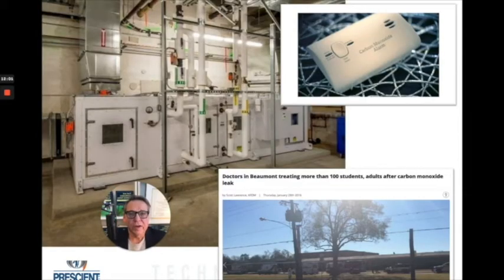Just how bad could it get? I was deposed a couple of months ago on a horrible incident that occurred in Beaumont, Texas at an elementary school. Close to 200 people were impacted when carbon monoxide in a mechanical equipment room got distributed through an air handler in the building and made lots of people sick. If you're in responsible charge of a mechanical equipment room that has naturally drafted equipment and air handlers, please make sure you've got a carbon monoxide detector in that room that reports to somewhere where people would know if there was a problem. In fact, now in the state of Texas, it's law that these be installed.